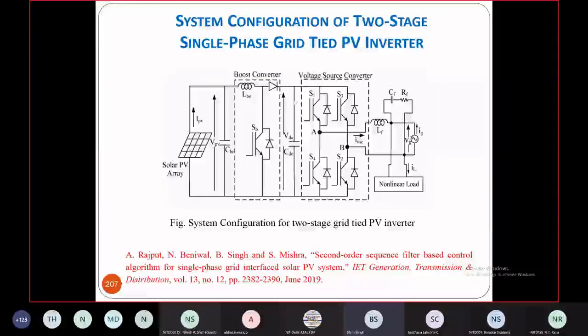Earlier, this DC link voltage is related with the AC side voltage. If you have an AC RMS voltage of let's say 220, then you have to take a DC link of typically 400. And to bring it to 400 volt at MPPT, the open circuit voltage in single stage should be certainly around 10 to 15% more. Only then can you get 400.